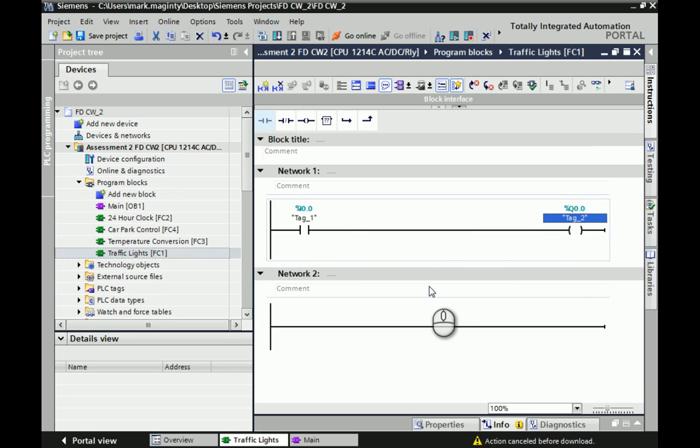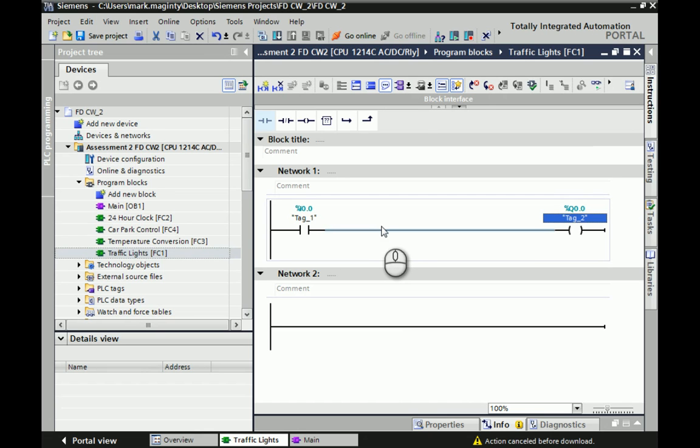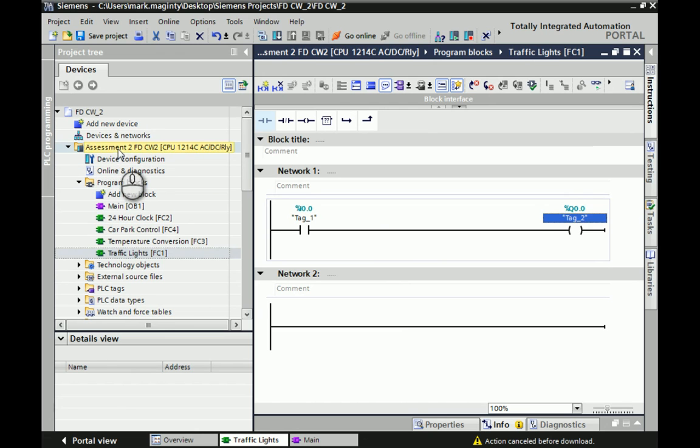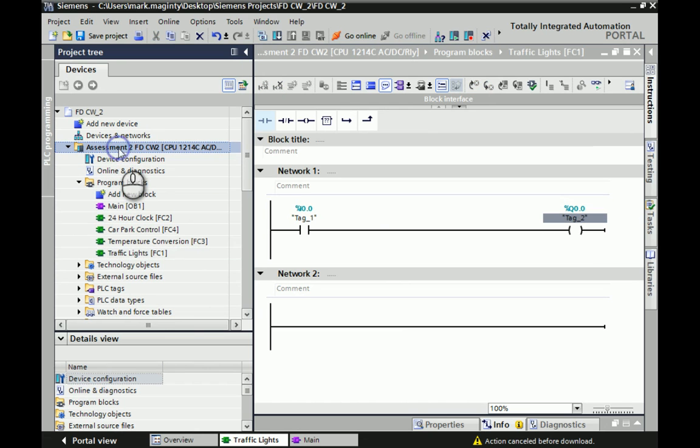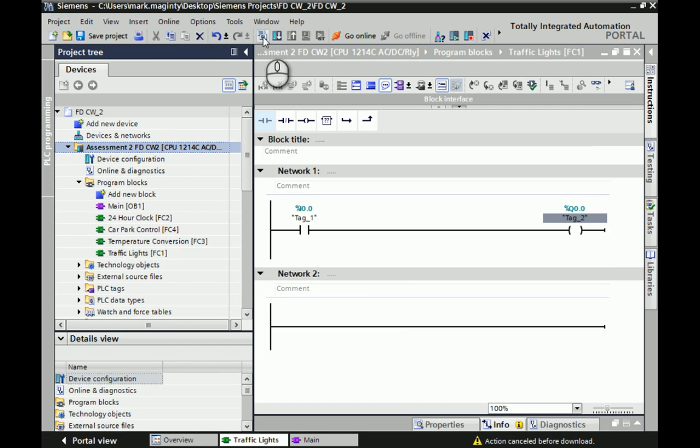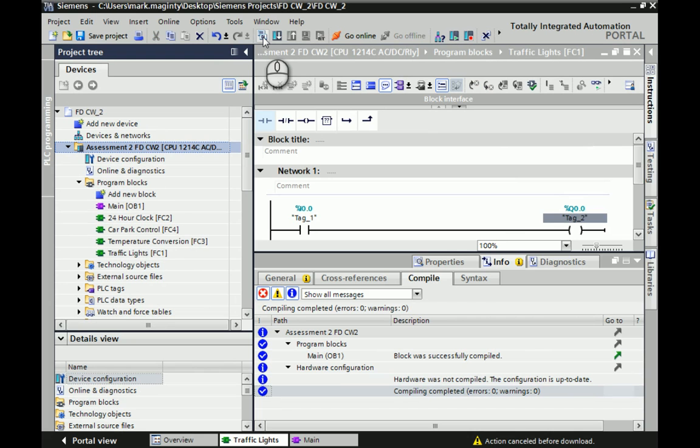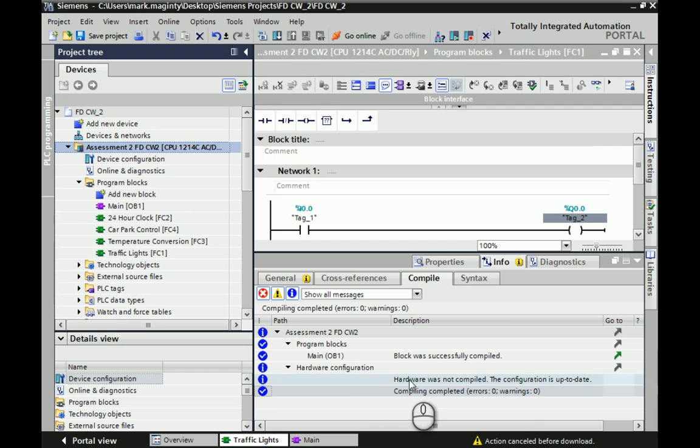So what we're going to do is run through the download procedure here and show you how the software is able to monitor and basically show you live what's happening. I have a couple of extra cables here that are just going to simulate the input becoming active. To test, what you need to do is go over to the left-hand side and left-click just once on the emboldened section. You can hit compile, and you should hopefully see that you have zero errors and zero warnings for all aspects that you're about to download.